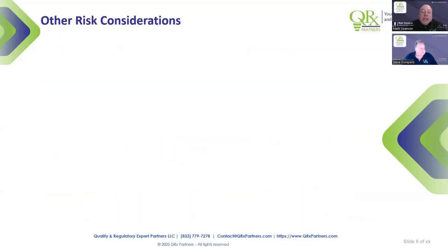And I think, Steve, that question that you asked, does it help meet a requirement of the regulations? Does it help meet the requirements of the ISO 13485 standard? If that is a yes, then that means it's in scope. If it's a no, then it's likely not in scope. Right. Yeah, and then there's some subtle area. There is some gray area in there, but if it's something that's required by regulation and your system is now managing that, the answer is yes, and you're going to have to think about this guidance.